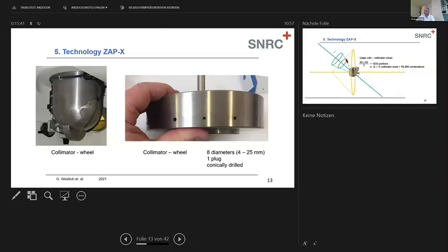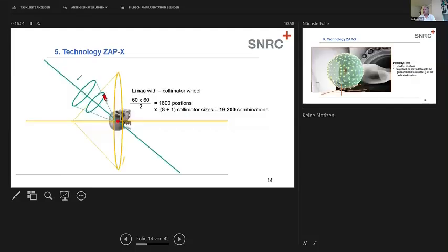It's, as I said, 16 centimeters of tungsten. It has 8 holes, 8 diameters between 4 and 25 millimeters. They're conically drilled. There's one plug position. That means there's one position where you disallow a beam to go through. And as I said, it's conically drilled.